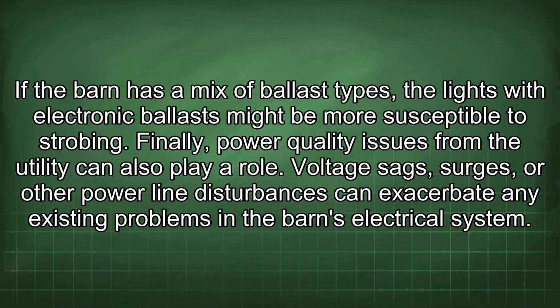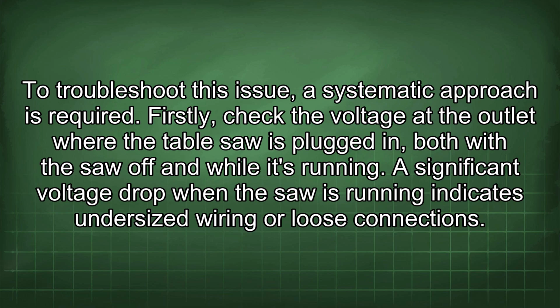Finally, power quality issues from the utility can also play a role. Voltage sags, surges, or other power line disturbances can exacerbate any existing problems in the barn's electrical system. To troubleshoot this issue, a systematic approach is required. Firstly, check the voltage at the outlet where the table saw is plugged in, both with the saw off and while it's running. A significant voltage drop when the saw is running indicates undersized wiring or loose connections.